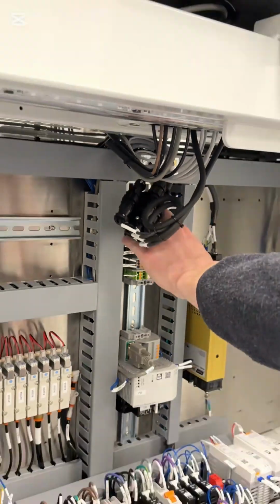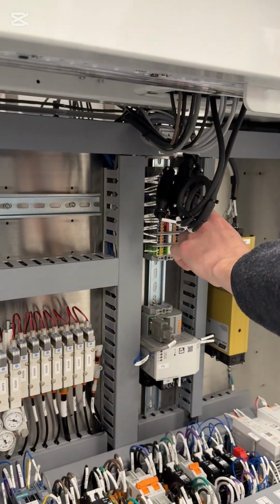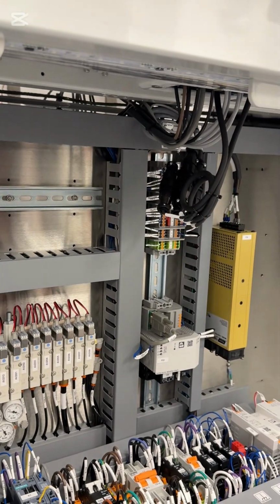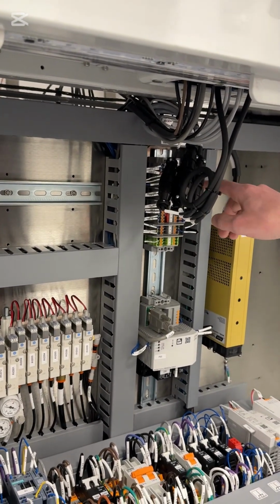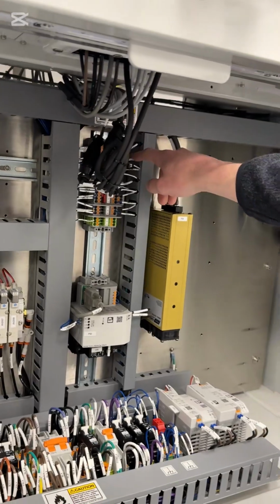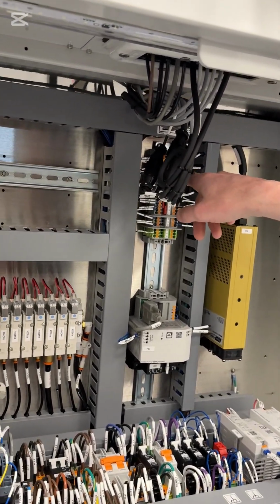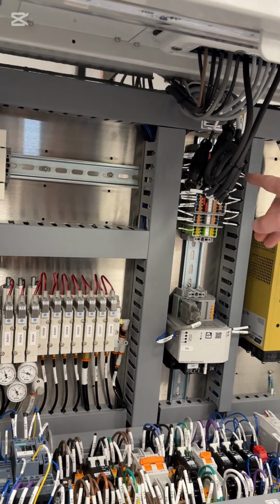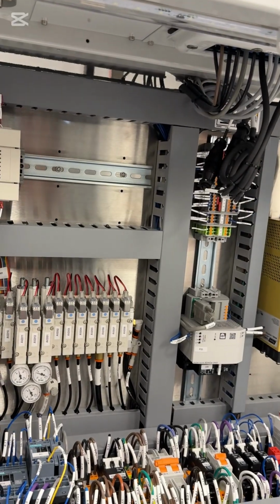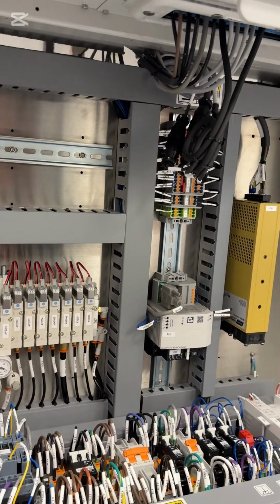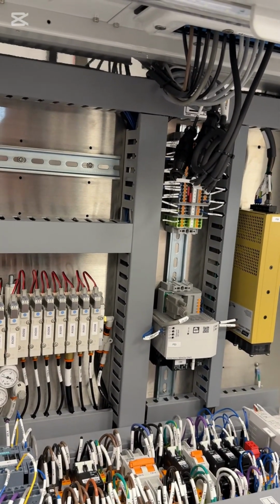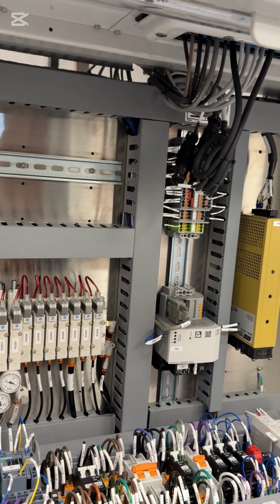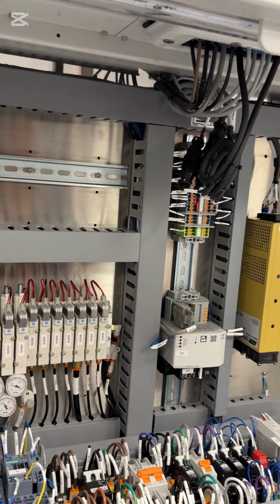You'll notice there are 3 more fuses up here, for 24 volt sensors. They all have LEDs, so if you see the LED turn on, there could be a chance that the fuse is bad, and you can double check that by checking the continuity.